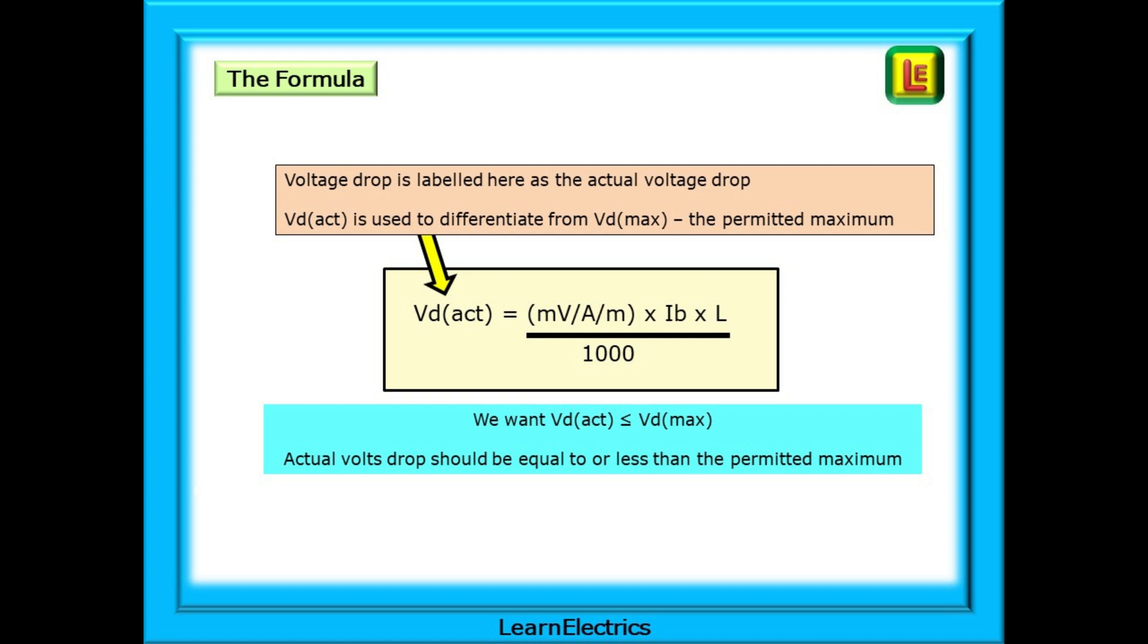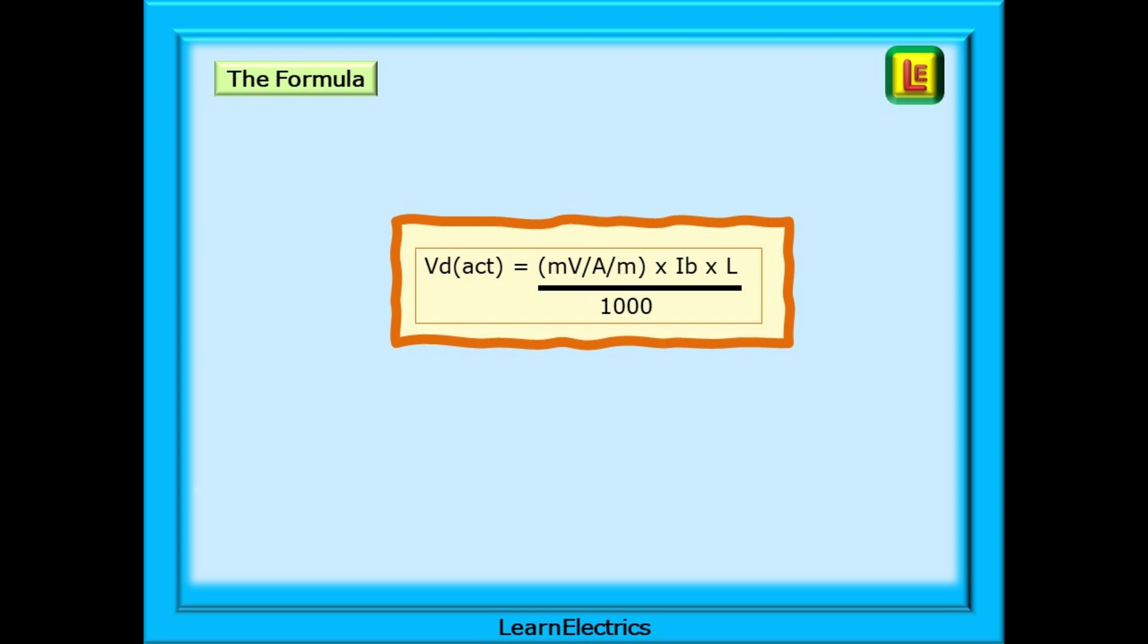In the formula shown here, voltage drop is the actual volts drop in the cables. We then compare this to the maximum permitted voltage drop shown in the previous table. But how do we know which voltage drop we are talking about? Actual or maximum? To avoid errors, I use VD(act) for the actual to differentiate from VD(max), the permitted maximum. We want VD(actual) to be not more than VD(max). Actual volts drop should be equal to or less than the permitted maximum. So this is the formula that we will be using. The next question is what do all the symbols mean? Not understanding the formula is often what makes people avoid using the formula. So let's put that right.